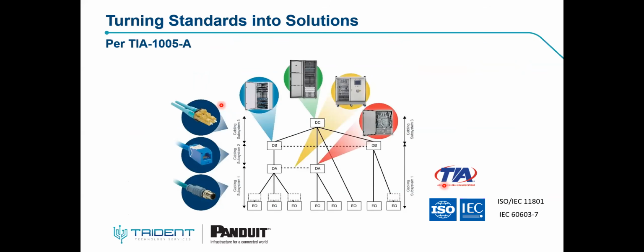You can review the steps that can be used for designing and deploying for the industrial environment. First, you need to study the future growth of your plant and take it into consideration before you start the design. As agreed, based on the TIA model, you have 3 subsystem connections. You can have subsystem 1 cabling, 2 or 3, using M12 for the automation machine, also copper and fiber for high speeds. Also, you need to know that you can install up to 6 connectors of copper per channel based on the TIA. Then the usage of the MICE rating.